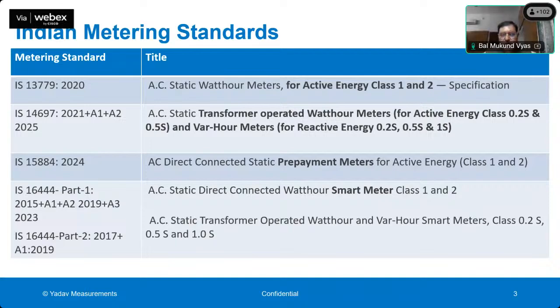Most of these smart meters can even send data almost every minute or even faster than that. So when smart meters are connected, the details about your consumption, details about your supply are available online to the utility: whether you are getting supply or not, whether you are consuming or not, what is the status of your load, voltage, various electrical situations. They are available online to the utility if a smart meter is connected. So that's one difference, that all smart meters have communication capability.